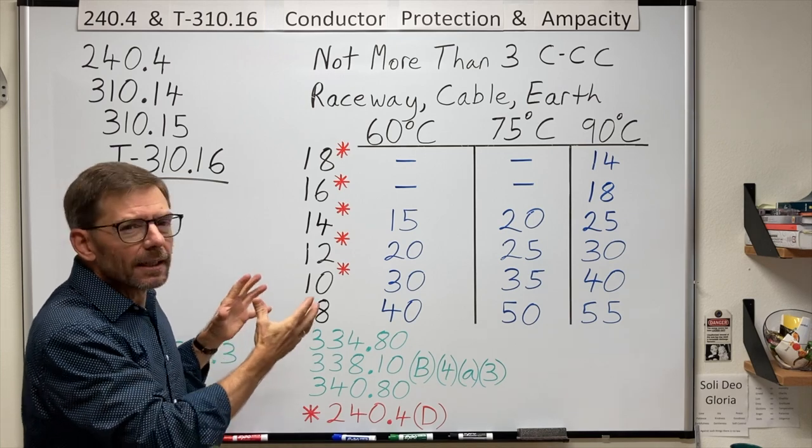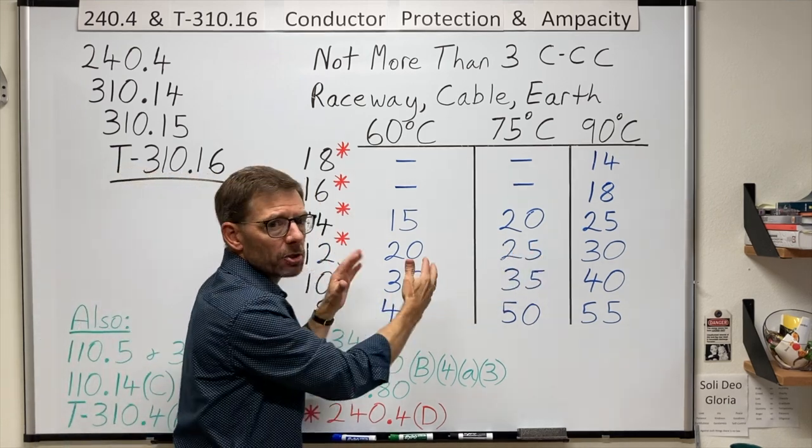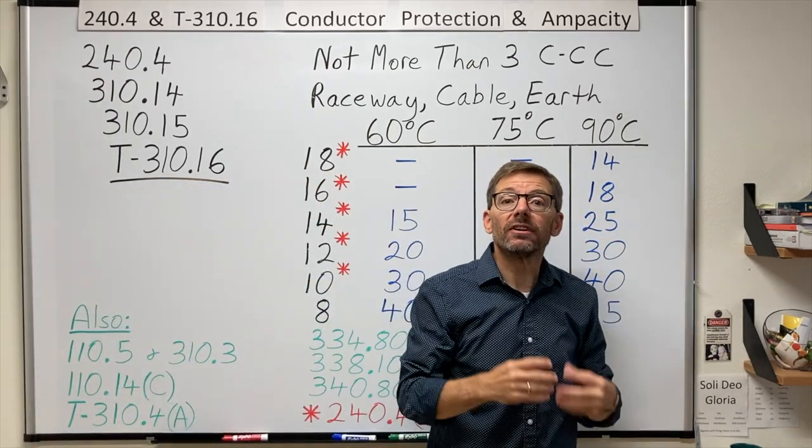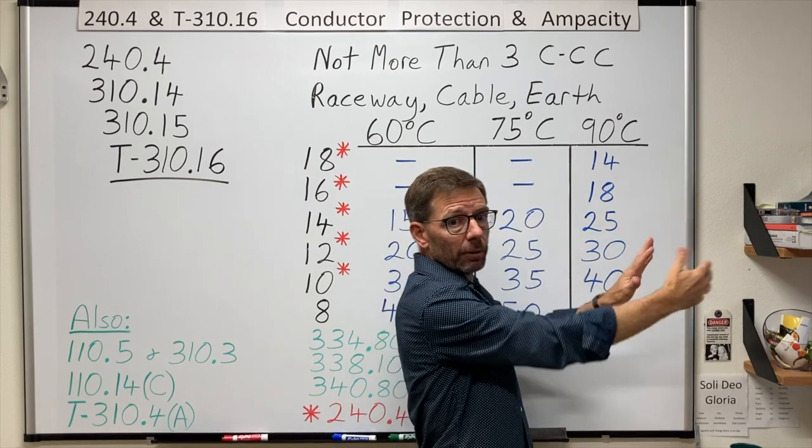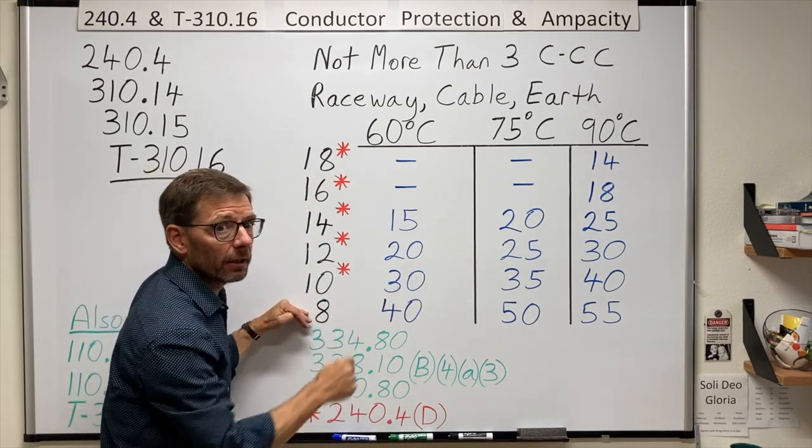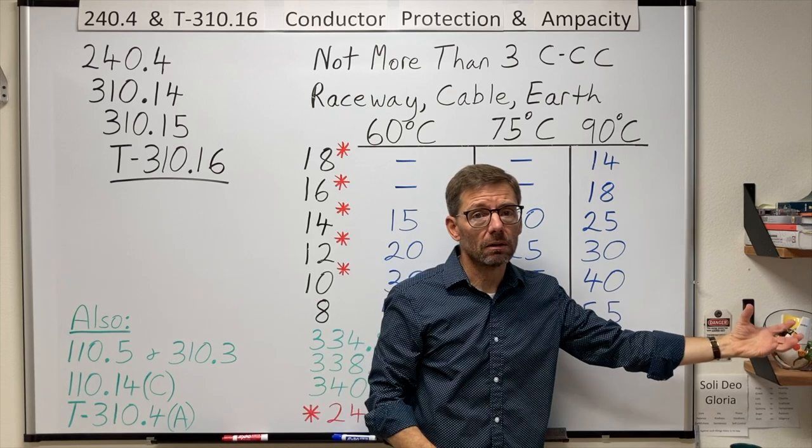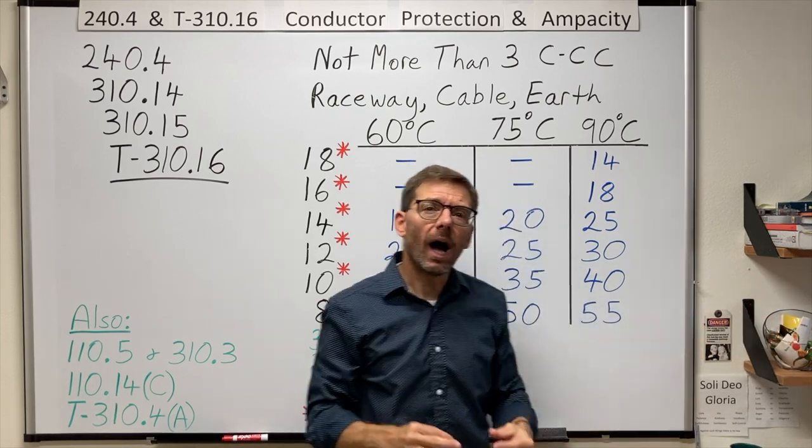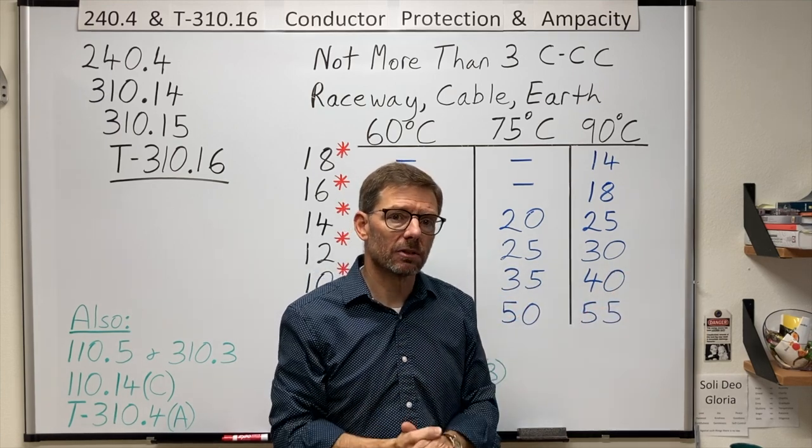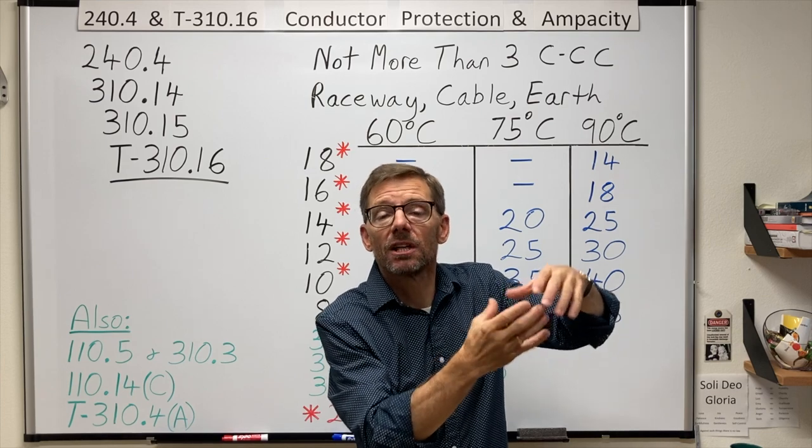Next thing I want to look at is that I only drew a small portion of the table. I just drew the copper side and a little bit of that. I didn't get into the bigger conductors. But there are three other columns that deal with aluminum. Copper on the left, aluminum on the right. The main thing I want you to notice now is that for the same size wire, a number eight copper or a number eight aluminum, the ampacities in the respective temperature columns are going to be lower in aluminum.